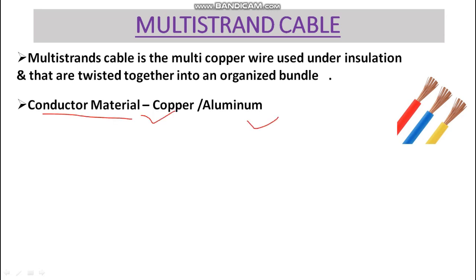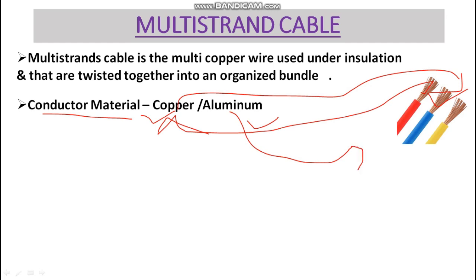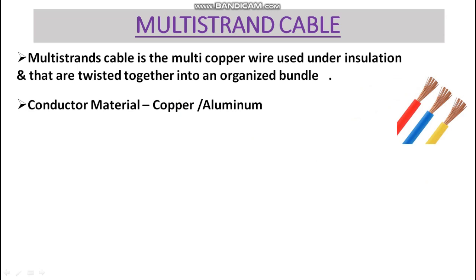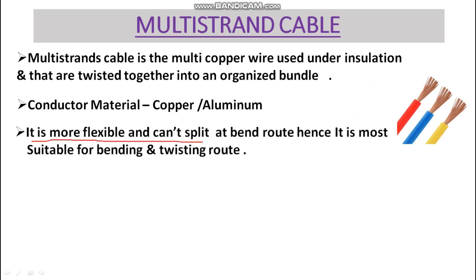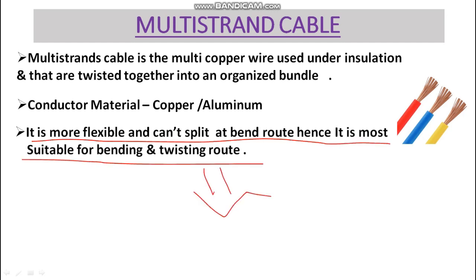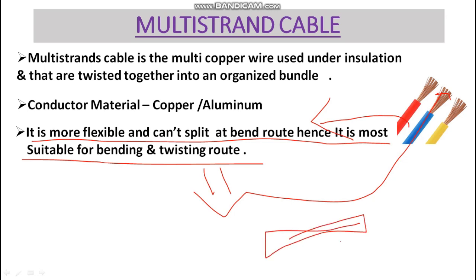The conductor material can be copper or aluminum. Mostly on the low voltage side it is copper type, and above that it can be copper or aluminum. This cable is more flexible and won't split at bend points, hence it is more suitable for bending and twisted routes because of the multiple strands of copper.